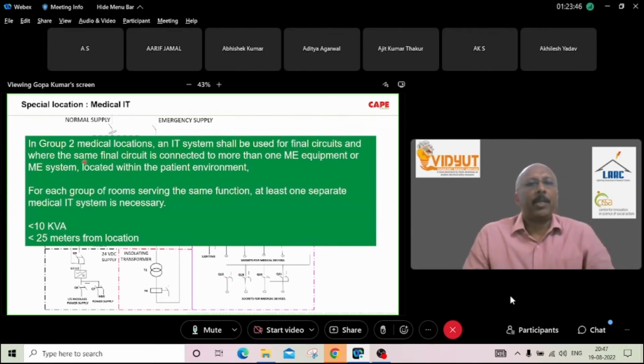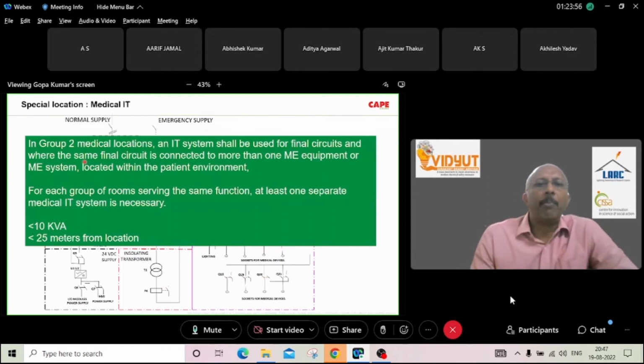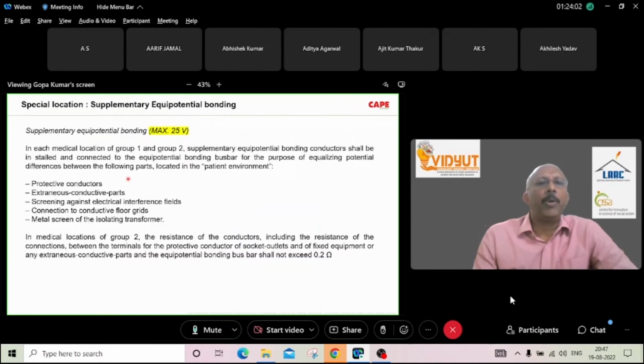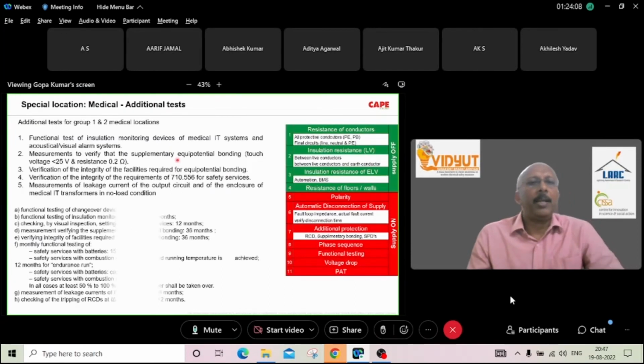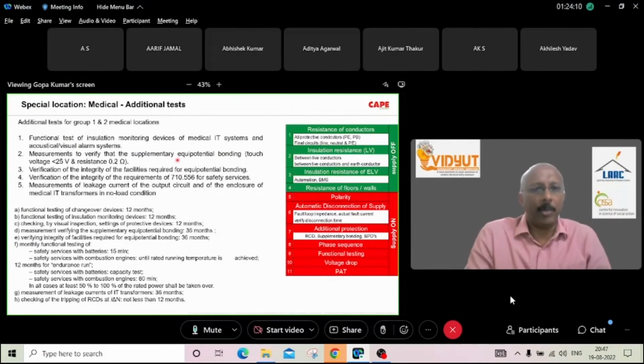Group 2 medical location is a place where the patient is connected with a lot of biomedical equipment. The supply disconnection will create a hazard. So continuity of supply is necessary for that particular area, and a lot of measures are already included in the standard. The touch voltage is 25 volt, and additional tests are also included.